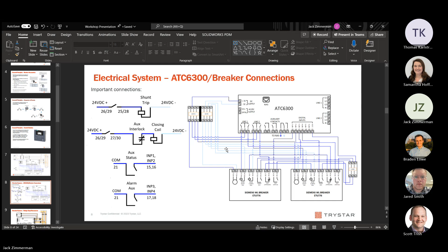All right, so voltage taps. This is another section, just breaking down the electrical system slowly, trying to make it simple. This side over here represents the bus bar and the breakers themselves. So this is the breaker switch over here, the actual disconnecting means on the bus bar, and then these are the bus bars themselves. We pull taps through little 12 gauge wires off of each side of the bus bar, the utility and the generator, or it could be another utility, whatever we're running. On this side, we have a fusible disconnect, which is very important. We'll go into service implications on another slide, but we can connect and disconnect power from the control system with overcurrent protection.